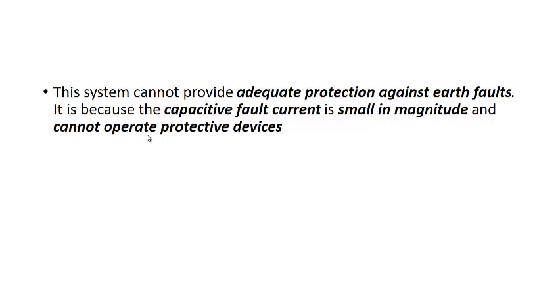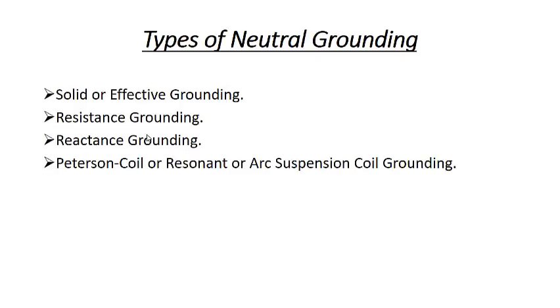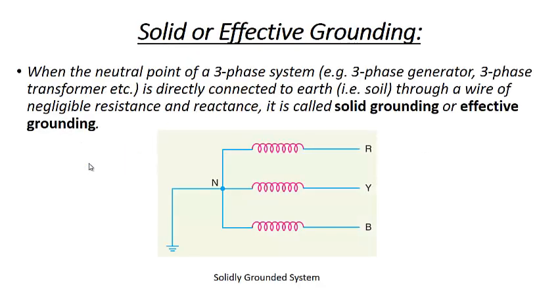Now coming to the neutral grounding, we have usually four types of neutral grounding: solid or effective grounding, resistance grounding, reactance grounding, and Peterson coil or resonant or arc suspension coil grounding. As I have told you, this will be the case when we totally nullify this capacitive charge and current. Now starting with the solidly or effective ground, what does this mean? When the neutral of the three-phase system, for example a three-phase generator or three-phase transformer, is directly connected to earth through a wire of negligible resistance and reactance, it is called solid grounding or effective grounding.